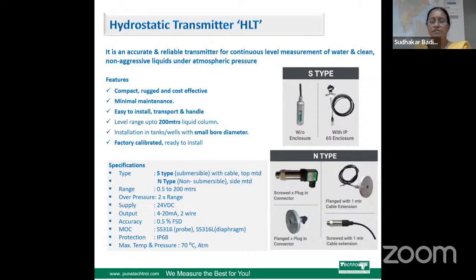Then this is a hydrostatic level transmitter. This is based on hydrostatic pressure measurement. So as the liquid level rises or falls, the pressure of the liquid column acts on the pressure sensor and that pressure is converted into 4 to 20 milliampere. This is available for range up to 200 meters. It can be installed in small tanks, in small inlet tanks, having small bore diameters. It is factory calibrated and ready to install. They are available as a submersible type and non-submersible type. The non-submersible type can be mounted on the side of the tank, whereas the submersible type can be submerged into the liquid.